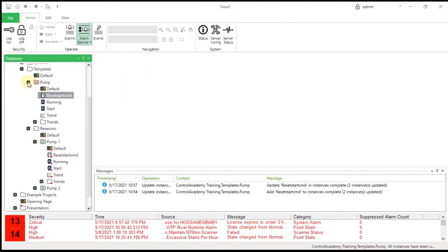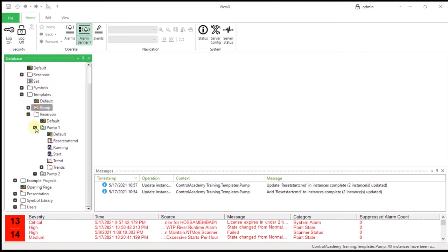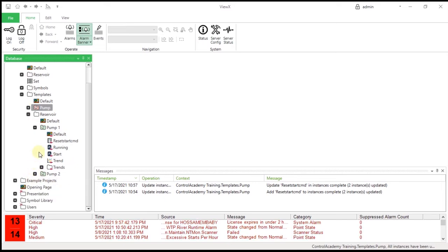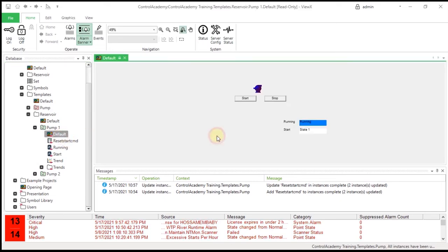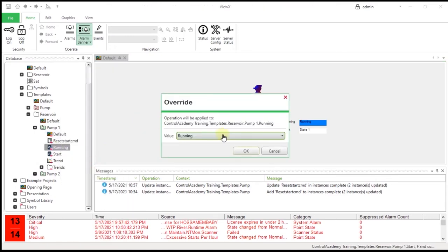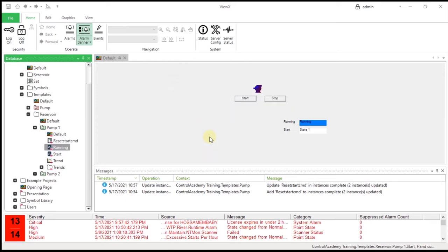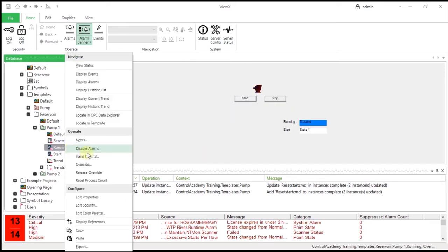Expand the Pump1 instance within the reservoir in the database pane. Verify that the logic program has been propagated to the instance. On the PumpMimic in the instance, click the Start button and verify that the correct output is turned on. Turn on the corresponding running point and verify that the start digital point is turned back to state zero by the logic program.